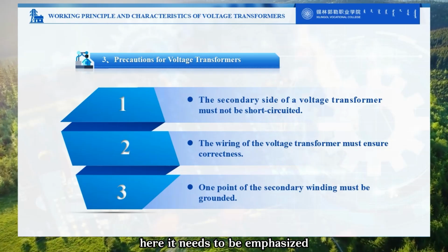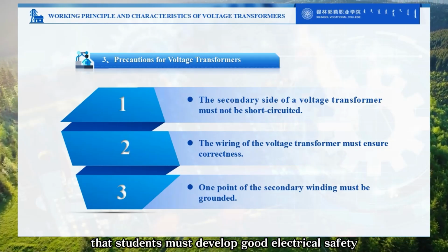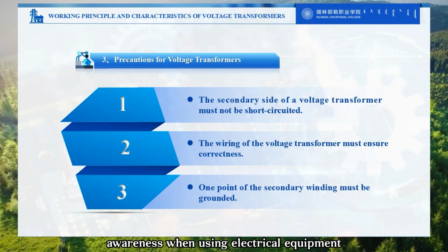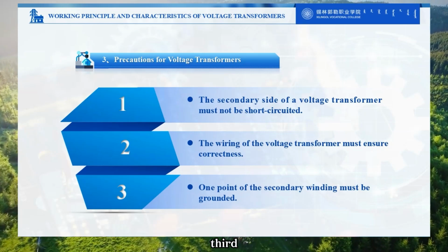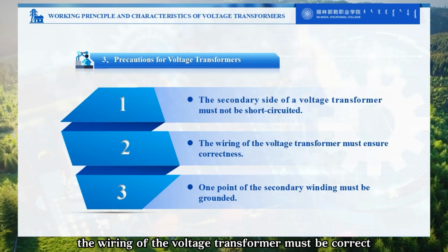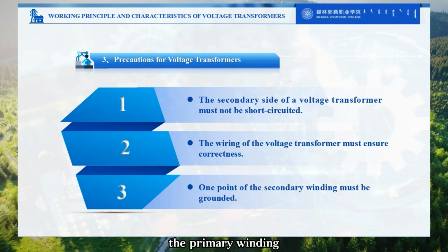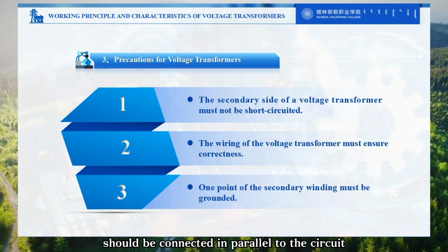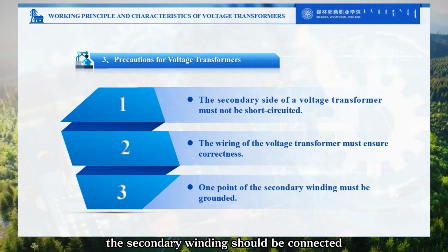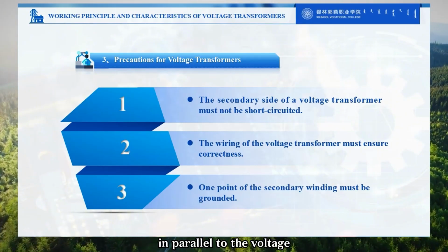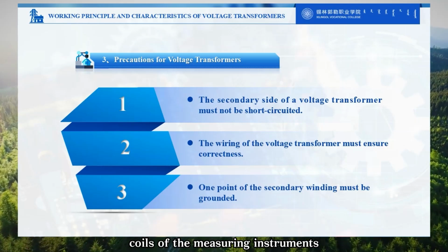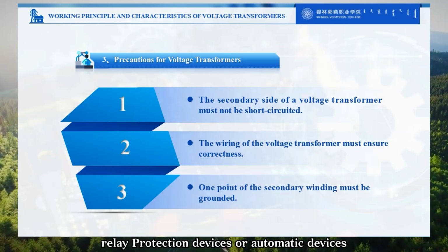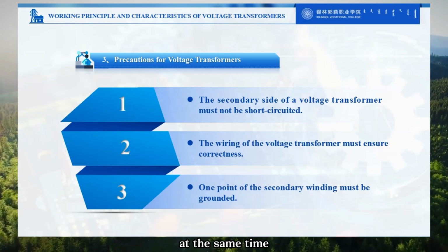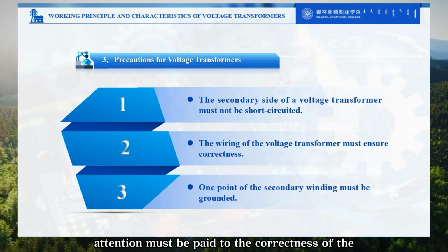Here, it needs to be emphasized that students must develop good electrical safety awareness when using electrical equipment. Third, the wiring of the voltage transformer must be correct. The primary winding should be connected in parallel to the circuit being measured. The secondary winding should be connected in parallel to the voltage coils of the measuring instruments, relay protection devices, or automatic devices. At the same time, attention must be paid to the correctness of the polarity.